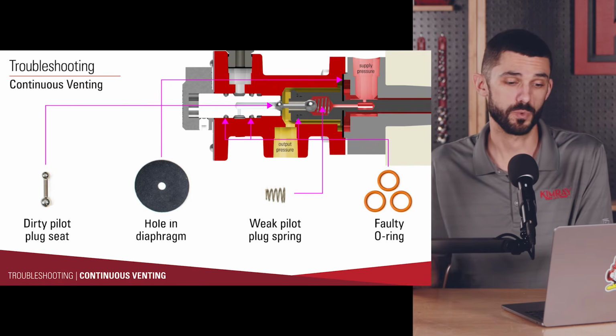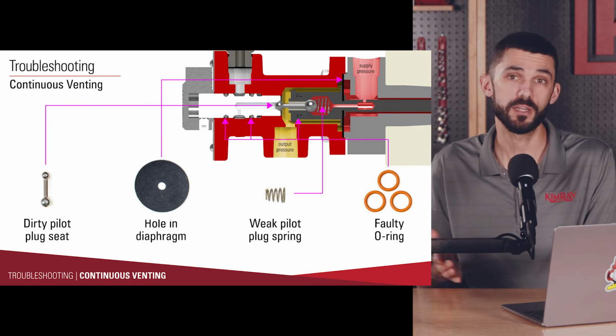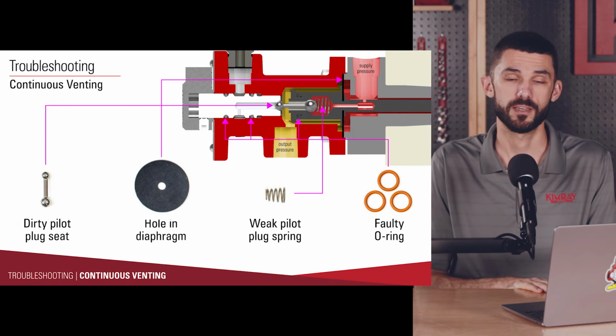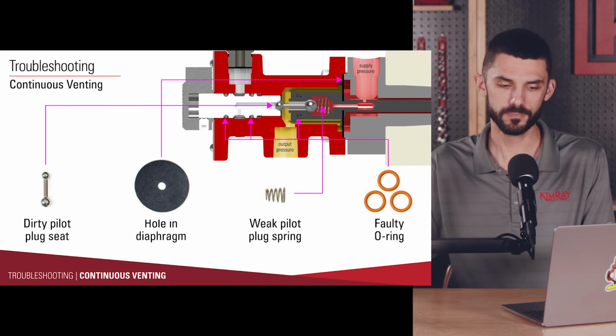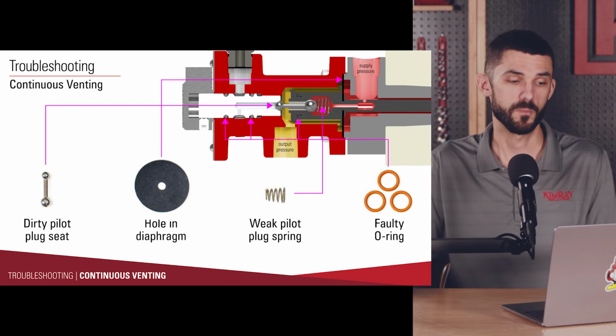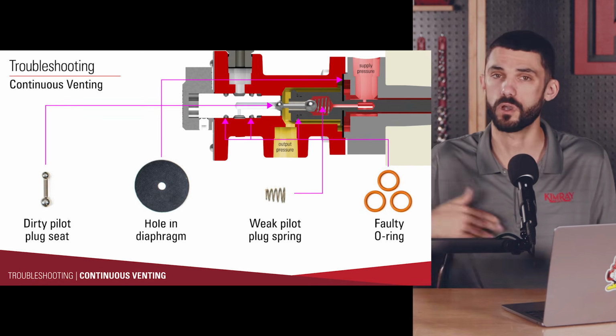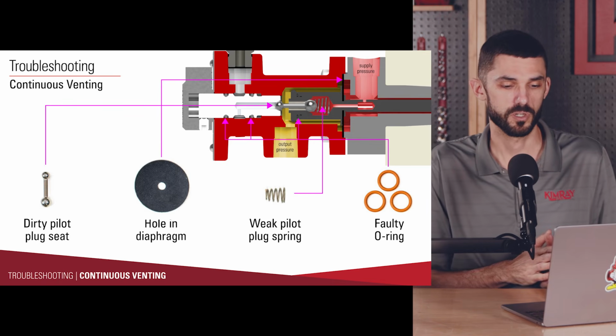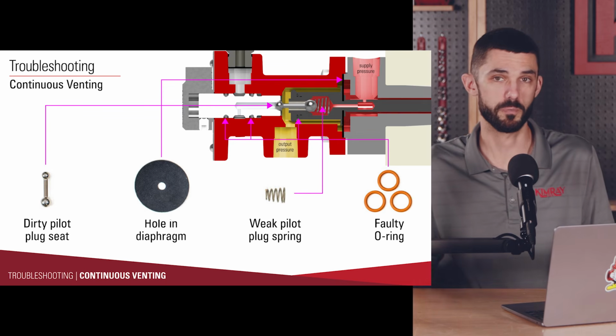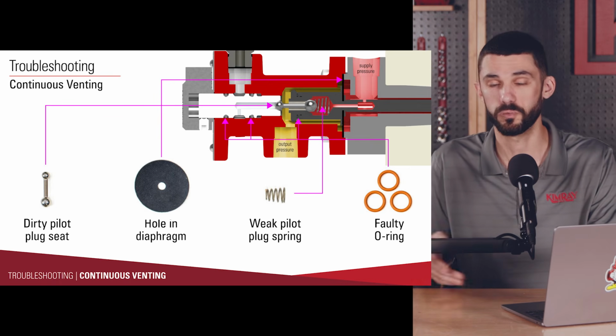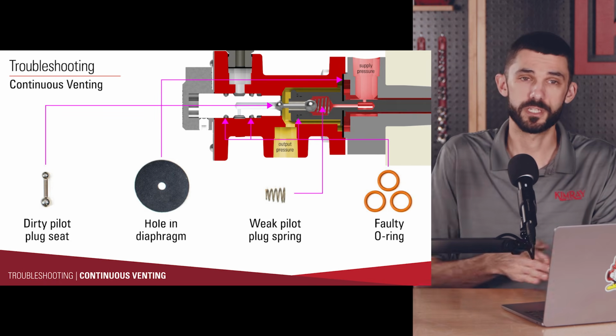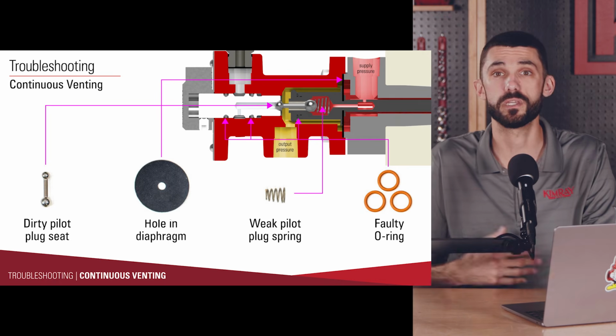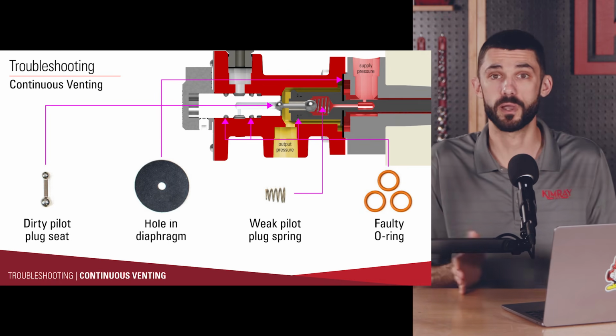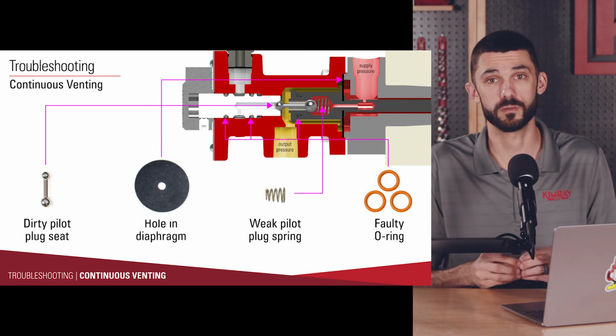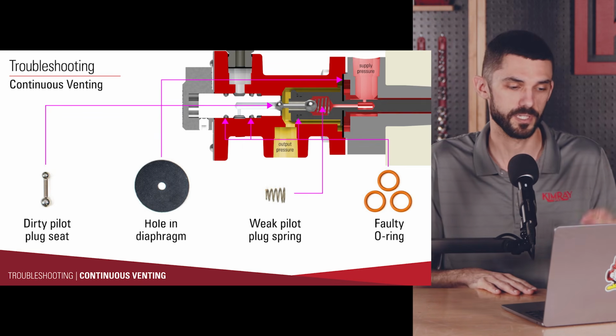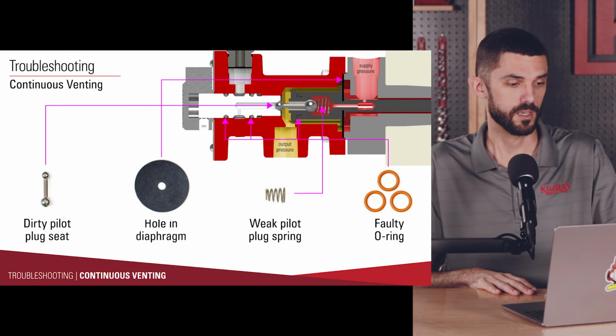If you're having issues with the T12 continuously venting, a few things to keep in mind. You might have wet or dirty supply gas. So just make sure that you're cleaning that up as best you can before it gets sent to the T12. There could be a hole in the diaphragm of the T12 that would cause continuous venting. You can repair these; if the diaphragm is damaged, you will need to replace the diaphragm. Another potential cause for continuous venting would be a weak spring. There is a spring on the pilot plug. It could be weak; sometimes even just stretching that out a little bit or replacing it completely with a repair kit should fix that problem.